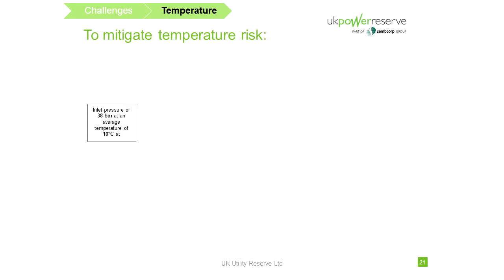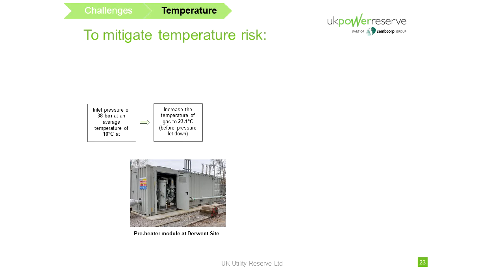Now, to mitigate this temperature risk, what I did was advise the team, saying, we've got an inlet pressure of 38 bar and an average temperature of 10 degrees Celsius, so let's incorporate a preheater module, which is the exact one I've got on site. This increases the temperature of the gas to approximately 23.1 degrees Celsius. And then with the subsequent pressure reduction to 7 bar, we're having approximately 8.1 degrees Celsius on the downstream pipeworks, which is within the range of between 0 and 20 degrees Celsius.